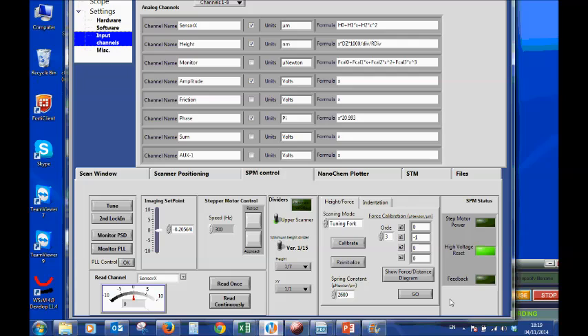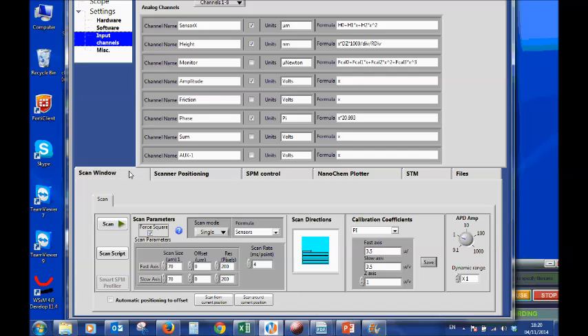Next step is to make sure that we have a calibration file. Now what I mean a calibration file is calibration and not linearization. So how do we create a calibration file? The same way like we do a regular calibration, we have to make sure that we have in the channels the x-axis and y-axis checked, and already if we're opening the input channels, also choose the sensor Y and also sensor X. Then we do a regular calibration procedure.